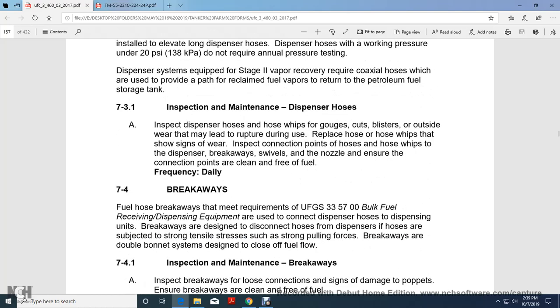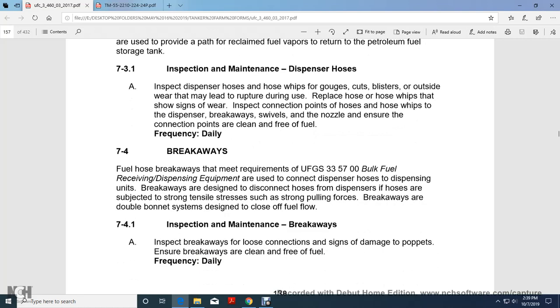Inspection and maintenance. Inspect dispenser hoses for whips, gouges, cuts, blisters, and outside wear, which may lead to rupture during use. Replace hoses and hose whips that show signs of wear. Inspect connection points of hoses, hose whips, the dispenser, breakaway, swivel, and nozzles, and ensure the connection points are clean and free of fuel daily.